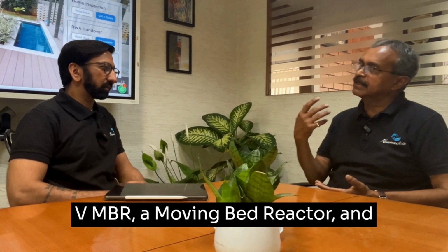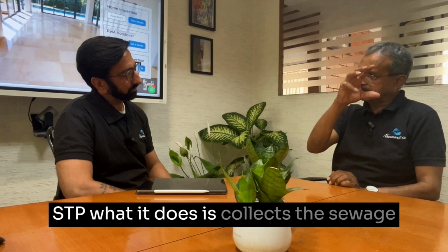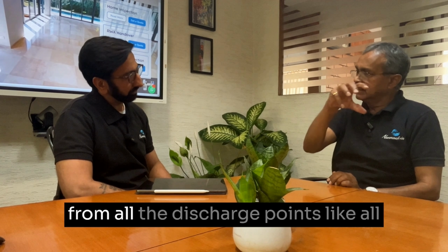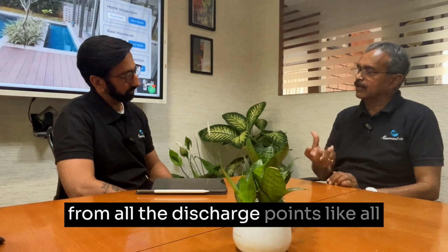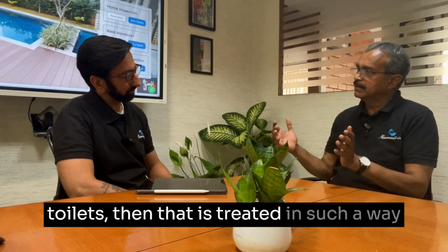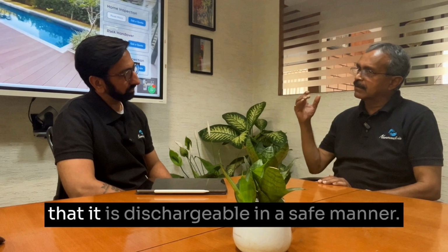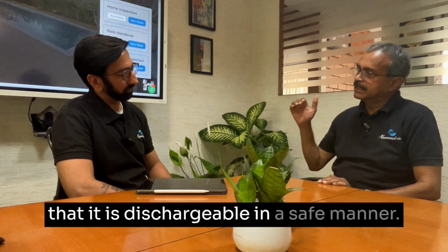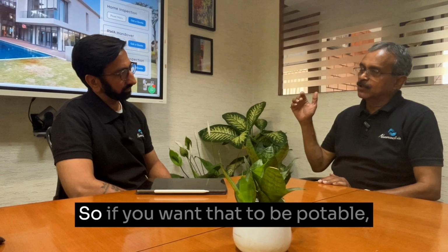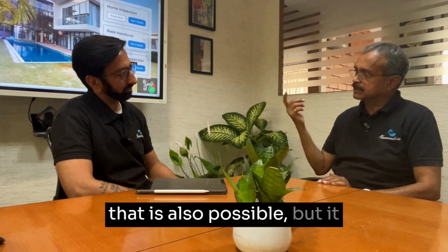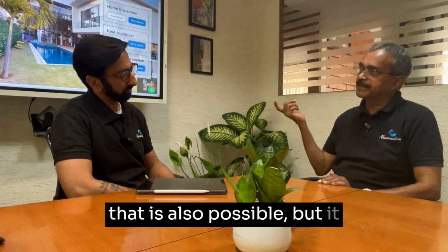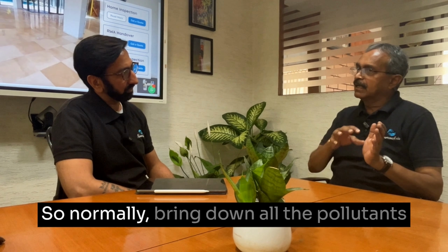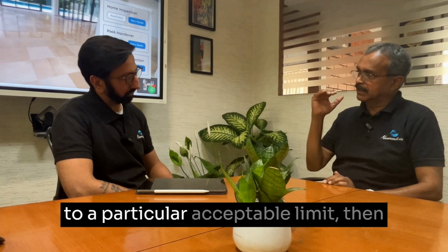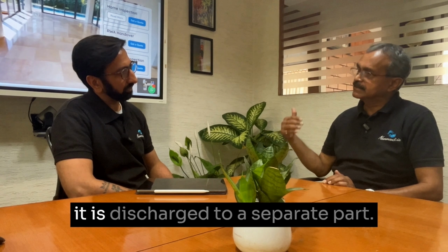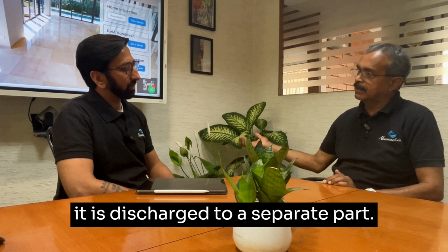Without going into the technicality of the process, basically what STP does is collect the sewage from all the discharge points like all toilets. Then that is treated in such a way that it is dischargeable in a safe manner. If you want that to be potable, that is also possible, but it requires a tertiary treatment. Normally you bring down all the pollutants to a particular acceptable limit, then it is discharged to a separate part.